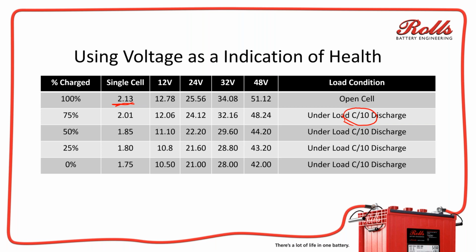You install the system, you charge it up to what you think is full. What I would do is cycle it. I would charge it up and watch the current going into the battery. If they're 24 S2690s, I would charge the batteries until the current dropped below 10 amps for an hour. Look at the current. Put your current meter on there and measure it.